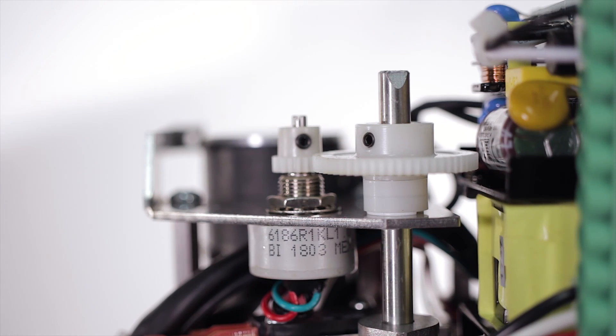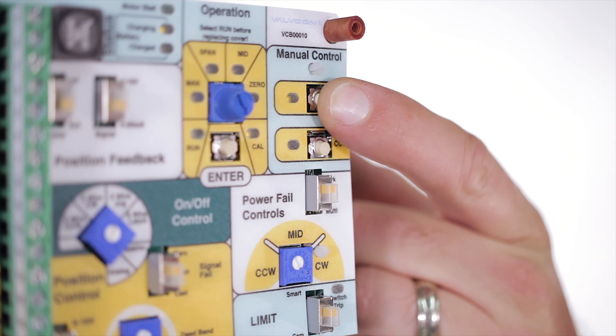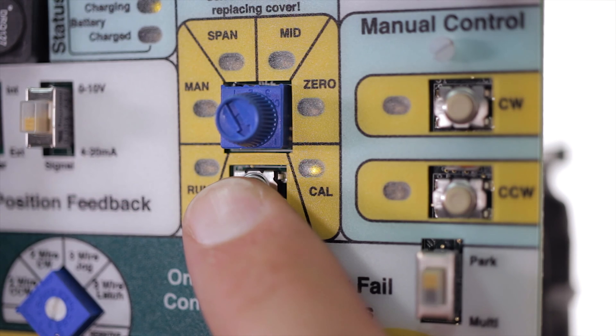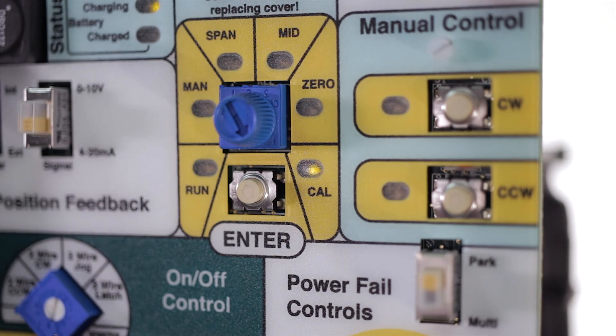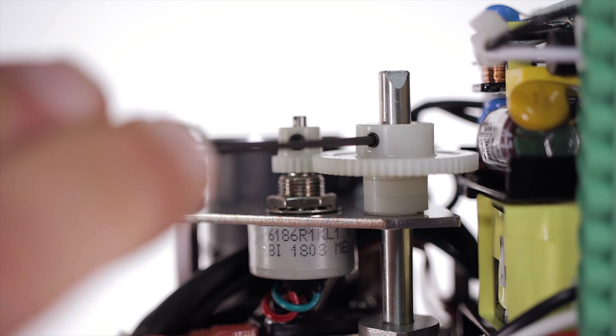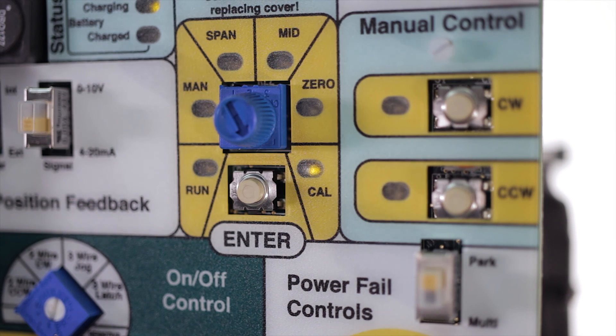Now we're ready to calibrate the potentiometer. Use your clockwise manual control button to drive the actuator fully closed. Hold the enter button down for two seconds until the calibrate LED light starts to blink. Loosen the set screw on the main gear behind the control board and slowly rotate the main gear clockwise while watching the calibrate LED light.